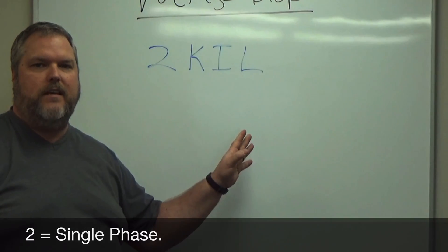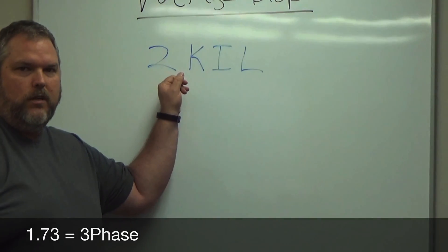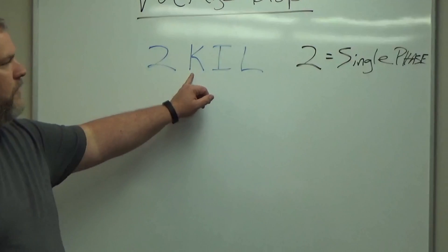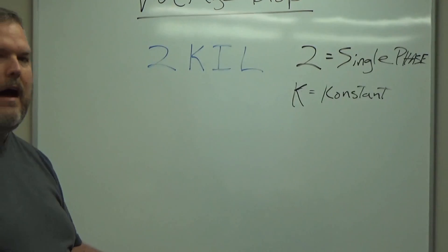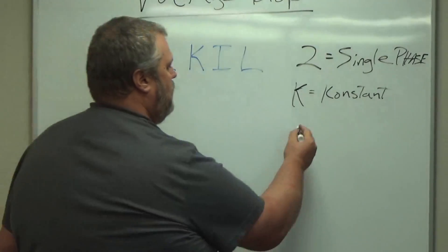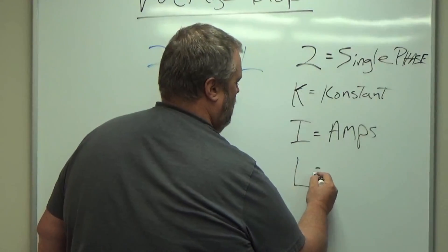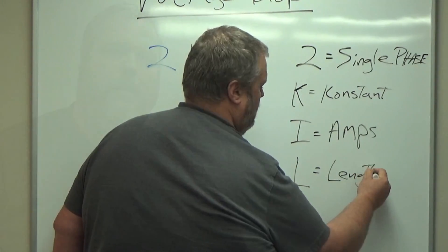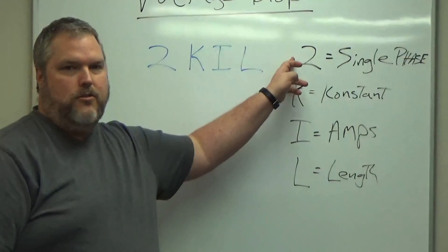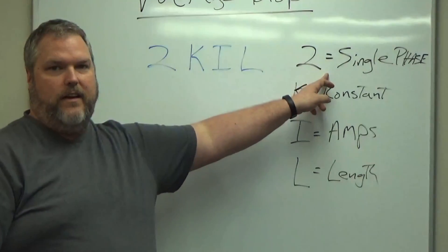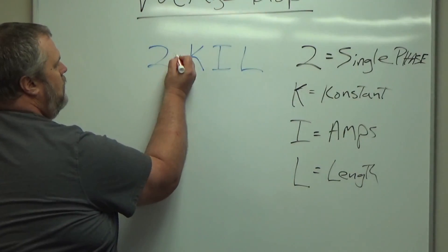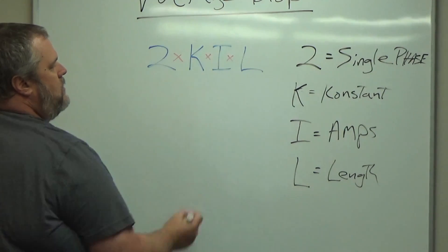One of the things you're going to need to understand is this is one of the biggest keys that we need to remember in doing our formula. So the 2 is going to represent single phase. The K is going to stand for our constant. I, we should know from basic Ohm's law, I equals Amps. And L is going to equal length. When it's written together, this is telling us we are going to do 2 times K times I times L.